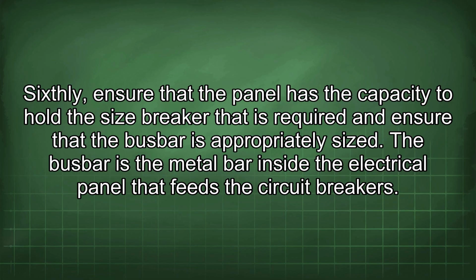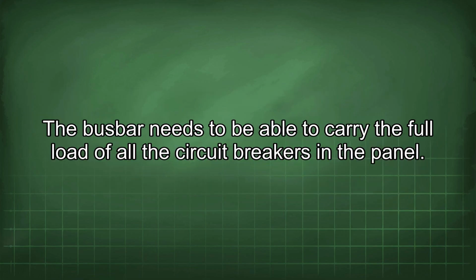Sixthly, ensure that the panel has the capacity to hold the size breaker that is required and ensure that the busbar is appropriately sized. The busbar is the metal bar inside the electrical panel that feeds the circuit breakers. The busbar needs to be able to carry the full load of all the circuit breakers in the panel.